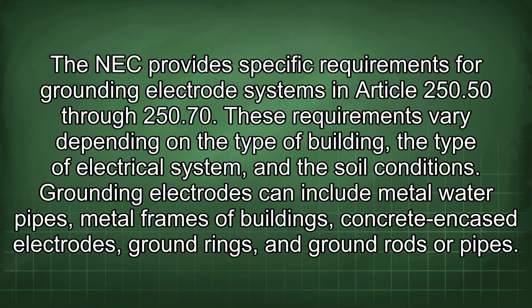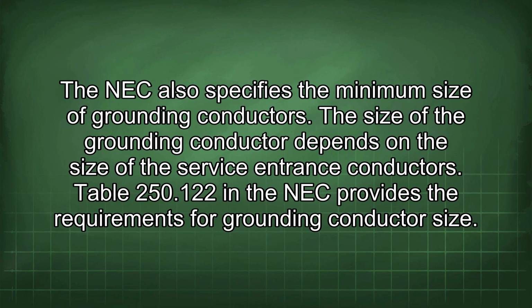These requirements vary depending on the type of building, the type of electrical system, and the soil conditions. Grounding electrodes can include metal water pipes, metal frames of buildings, concrete encased electrodes, ground rings, and ground rods or pipes. The NEC also specifies the minimum size of grounding conductors. The size of the grounding conductor depends on the size of the service entrance conductors. Table 250.122 in the NEC provides the requirements for grounding conductor size.